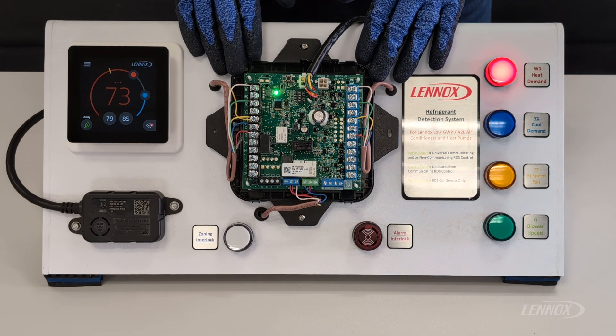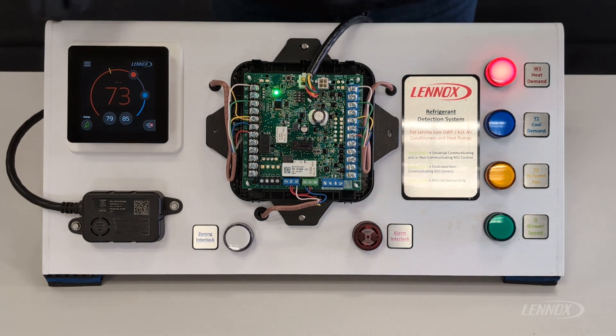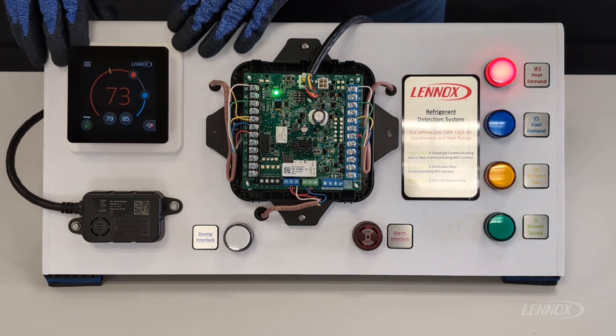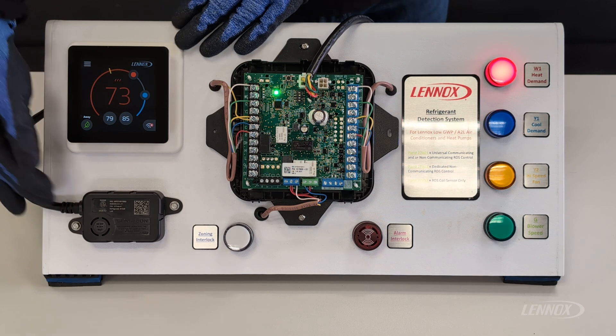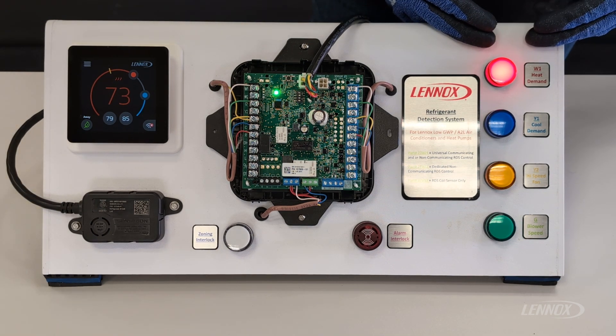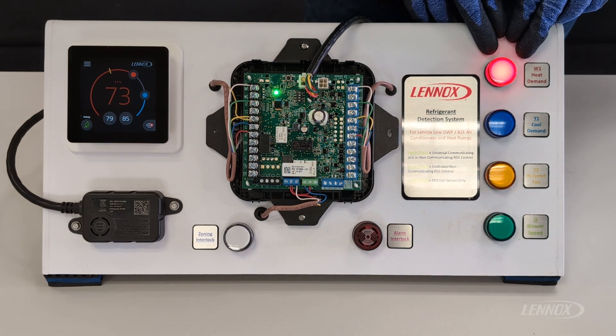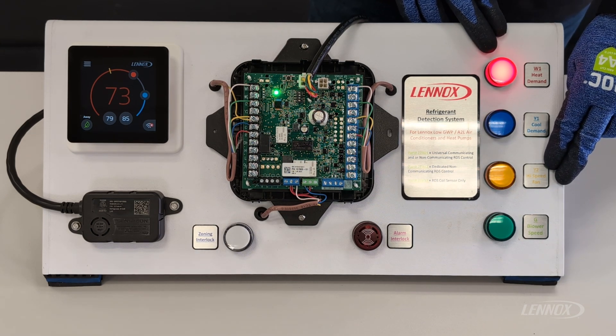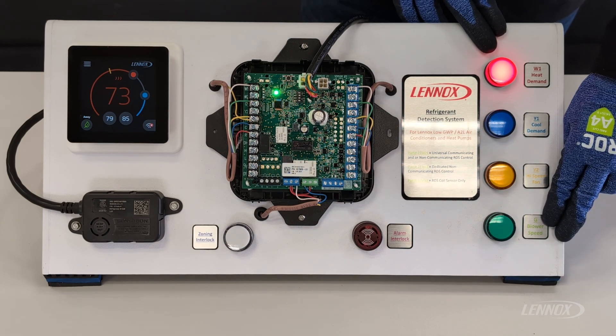Front and center here we have our RDS control, or our refrigerant detection system control. Next to that we've got our Lennox L40 thermostat connected, beneath that is our refrigerant detection sensor, and then along the outside of this training unit we have some different LEDs that indicate different system outputs. This red LED would be a W1 heat demand, blue would be a Y1 cooling demand, yellow would be a Y1 fan demand, and G would be our blower enable. Along the bottom we have our alarm interlock light and our zoning interlock light.